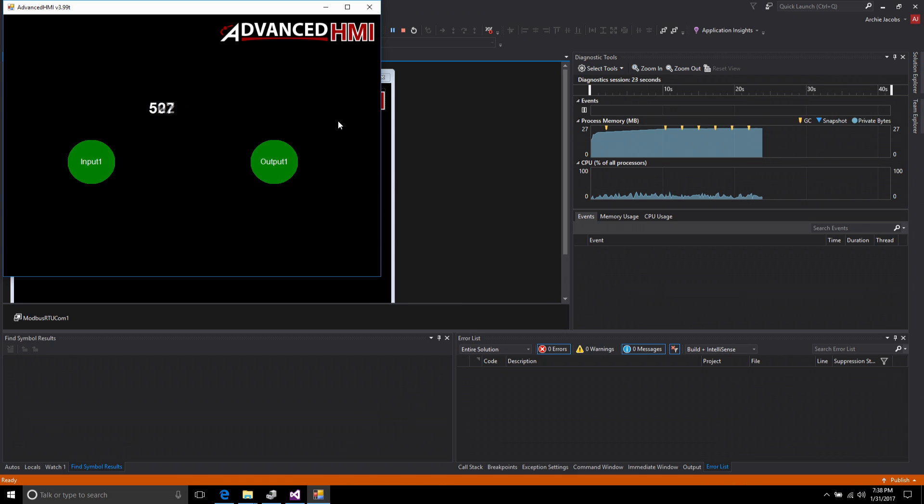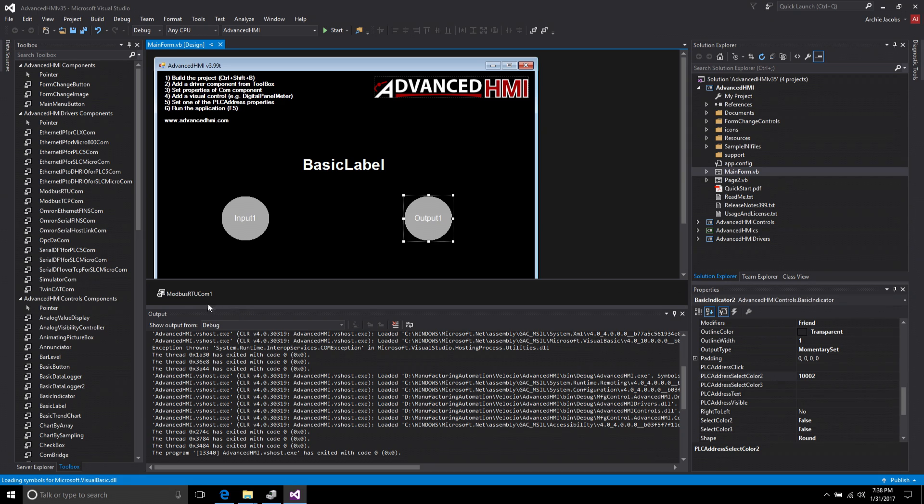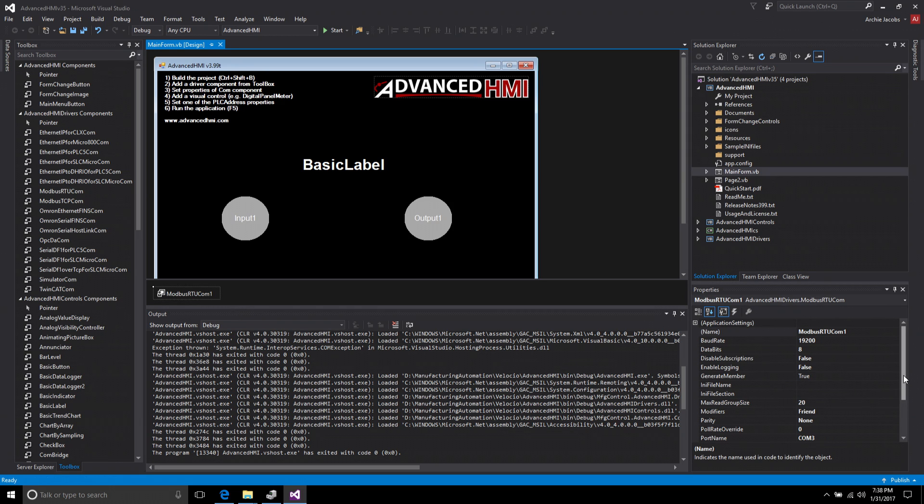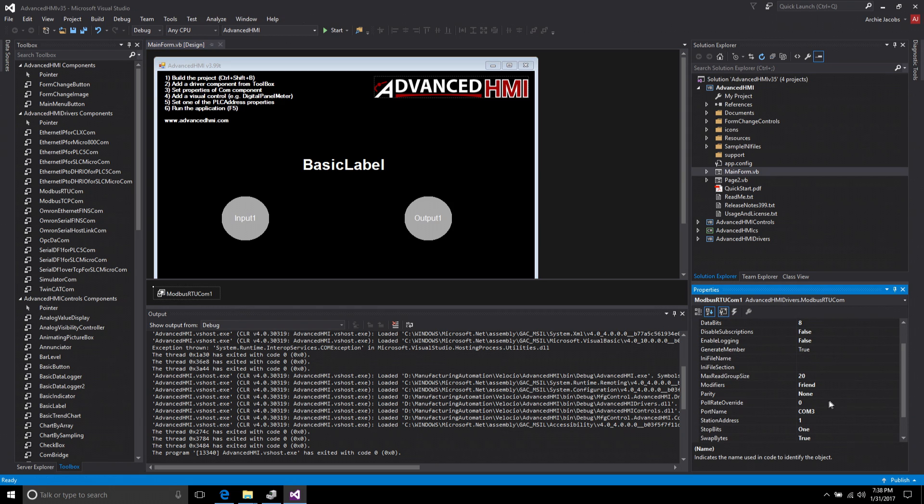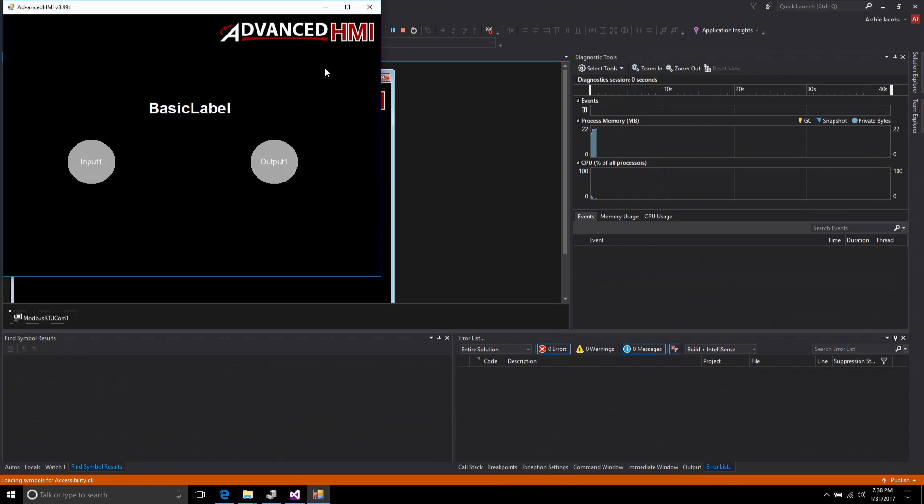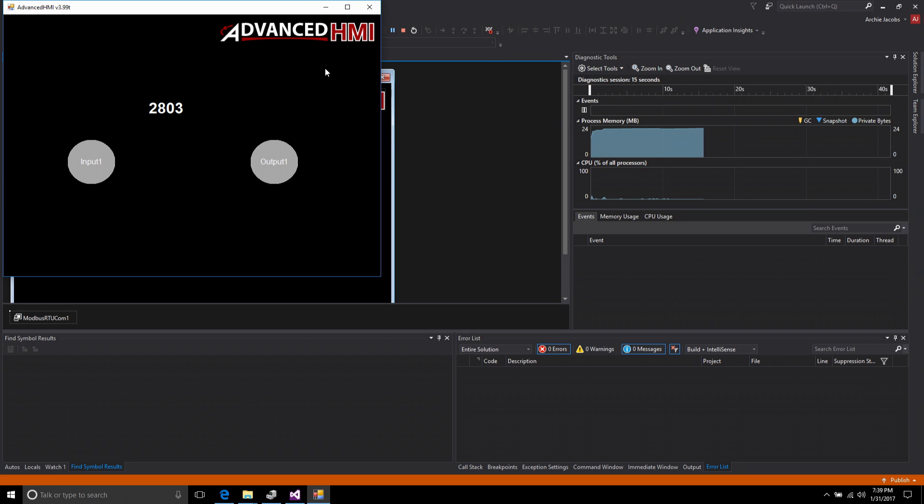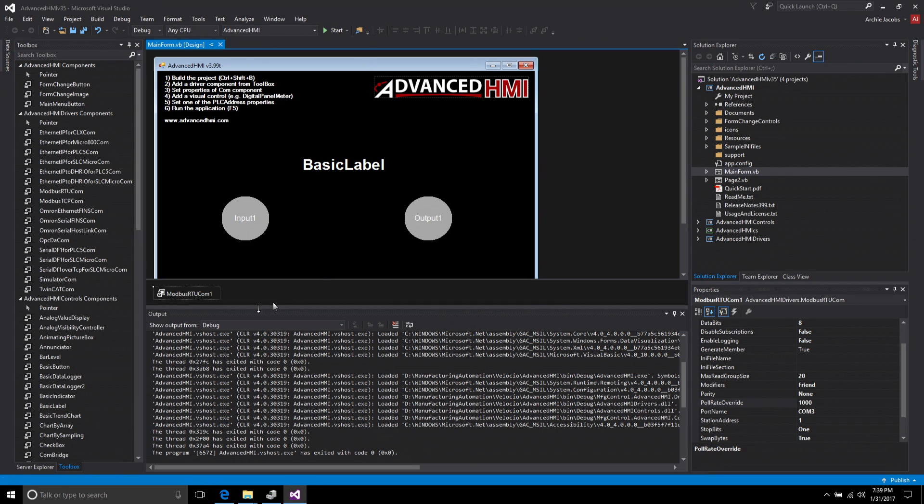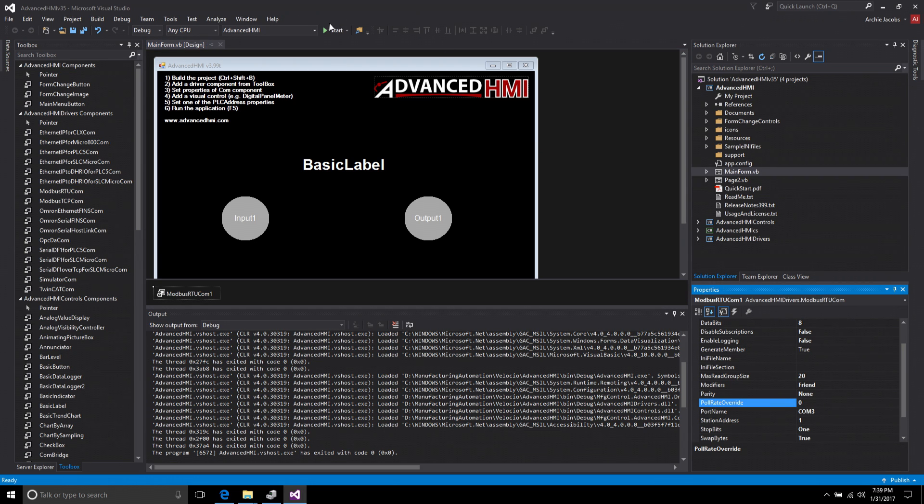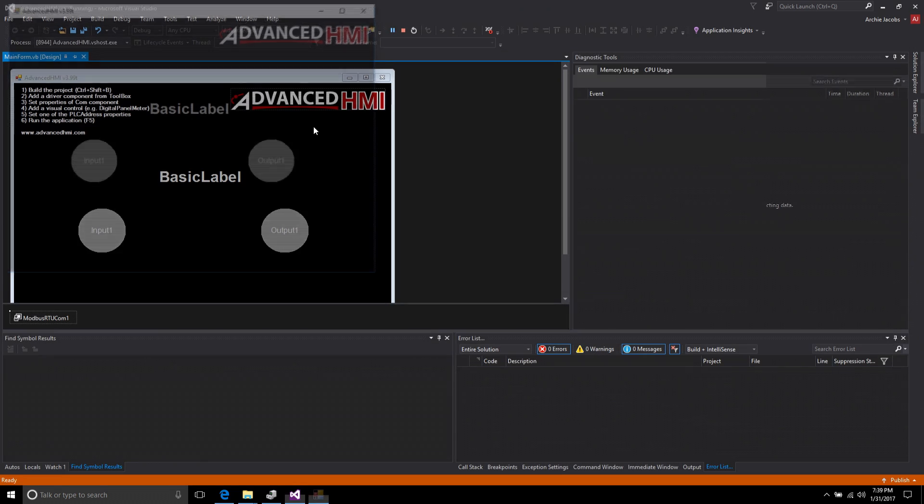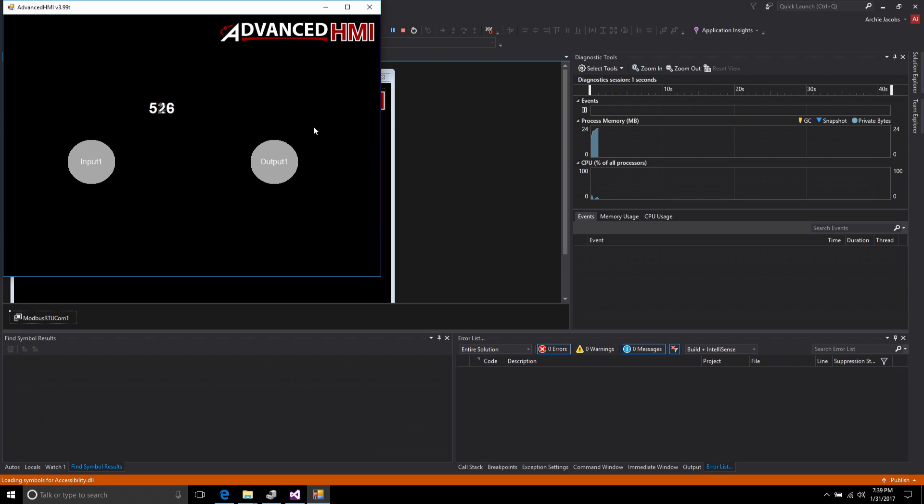Now it's extremely fast because I have the poll rate override down to 0. So you see they look like they're happening simultaneously, which they kind of are, because the PLC is also refreshing them very fast. Now let me go back and change the poll rate override just so we can kind of see. I'm going to make it 1000. That means there's a one second delay in updating. So now you'll see my update. You'll be able to tell from my label how slow it's happening. So now if I switch, say I switch on, there's a little bit delay, they come on, switch off. So it can basically be up to a one second delay. So you see the difference there with that poll rate override. If I go back to poll rate override of 0, it's pushing this communication link as fast as it possibly can, which is very fast. You can almost see that it's almost within the milliseconds that it's updating.